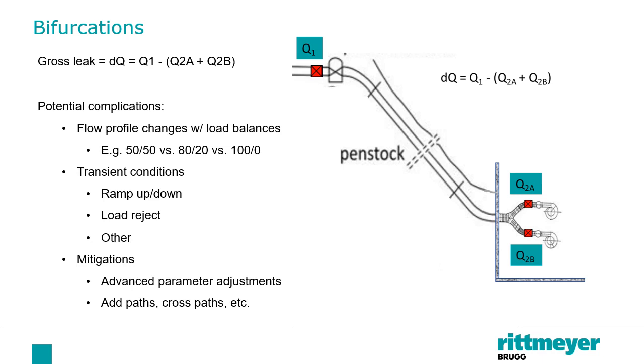They are a little more expensive. The serviceability is a little more difficult. But again, this is a better measurement location, and you have to make the trade-offs for that particular site. If you are going to do internally mounted transducers, then I encourage you to check out Rittmeyer's unique cable protection system. You have to protect the coax cables inside the penstock until you're able to pull them out. And Rittmeyer has a very unique solution that you should check out before you make any decisions on internally mounted transducers.